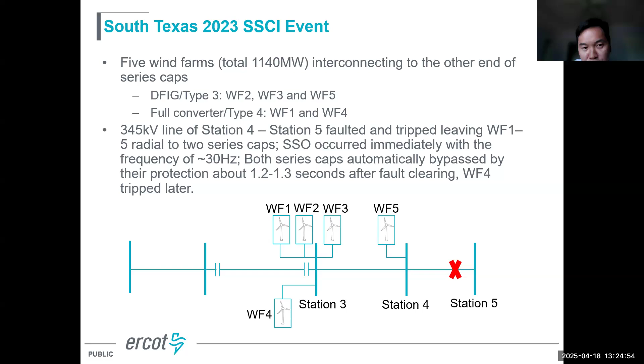It looks like it's very hard to replicate SSCI events in PSCAD simulation. And I think the reason we have these events is really that tuning the SSO damping control with changing system conditions is very challenging. I'm not saying it doesn't work, because we still have one privately owned series compensation with DFIG machines connected to it, and they have been operating for maybe 10 or 15 years, and it works fine.